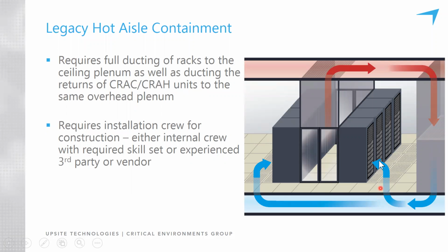I'll step back and answer one of the questions that's already been asked, which is what's better, hot aisle containment or cold aisle containment? And studies, both theoretical CFD analysis and in-the-field studies, have proven that hot and cold aisle containment, if done well, are equally efficient. And I emphasize that "if," because it's a potentially big if. Cold aisle containment is much more common. I'll explain that in just a moment.